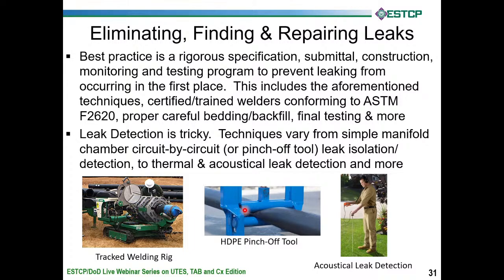I was talking literally today with a contractor who kind of specializes in this. They have been called in on a dozen projects, and the key thing he said to finding the underground leaks acoustically is to have a good set of as-built drawings where you actually could literally come out on the ground and spray out the loop that's leaking. So, the idea is you go to the manifold chamber, you find out which of the loops are leaking.